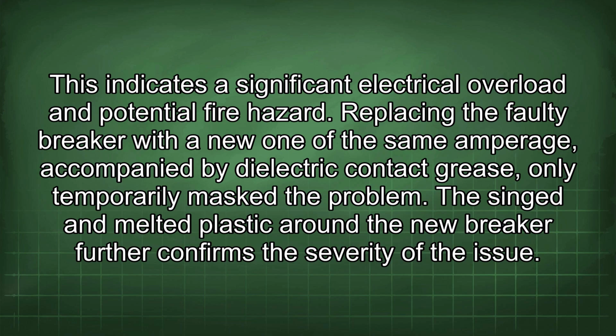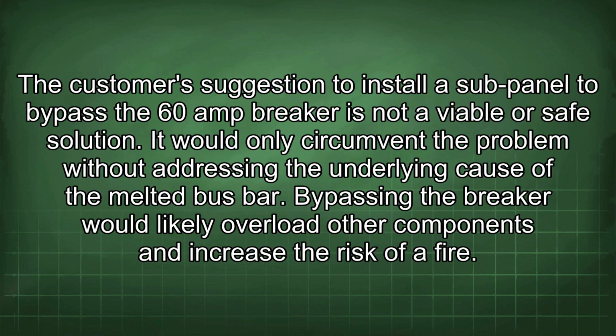Replacing the faulty breaker with a new one of the same amperage, accompanied by dielectric contact grease, only temporarily masks the problem. The singed and melted plastic around the new breaker further confirms the severity of the issue. The customer's suggestion to install a sub-panel to bypass the 60-amp breaker is not a viable or safe solution. It would only circumvent the problem without addressing the underlying cause of the melted bus bar. Bypassing the breaker would likely overload other components and increase the risk of a fire.